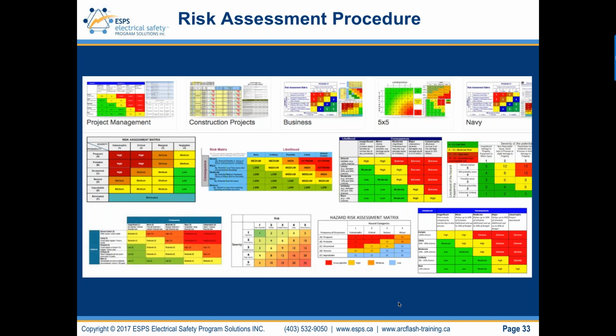So that's what concerns me, is there's a ton of information out there for industry to reference on what a risk assessment procedure is. But what I find is that companies aren't implementing a risk assessment procedure. They're neglecting it. They're just saying that completing an arc flash risk assessment and a shock risk assessment is the risk assessment procedure, which it is not. Arc flash and shock risk assessments are components of the overall risk assessment procedure in NFPA 70E or CSA Z462.